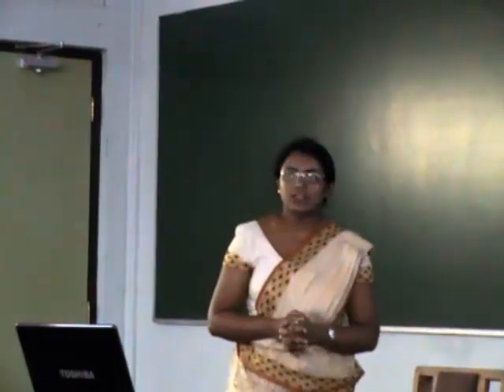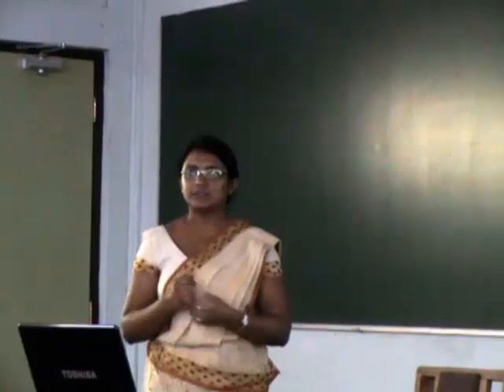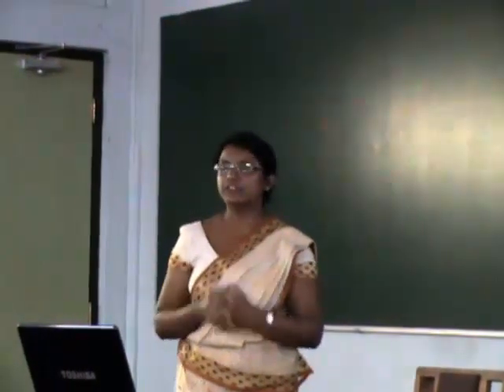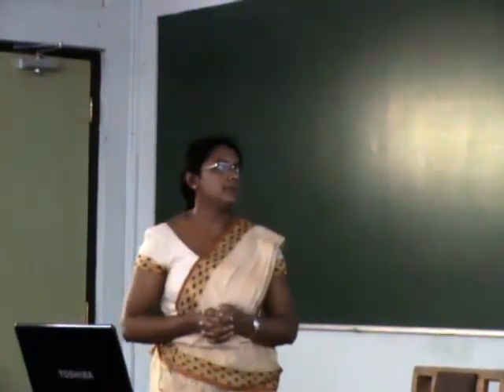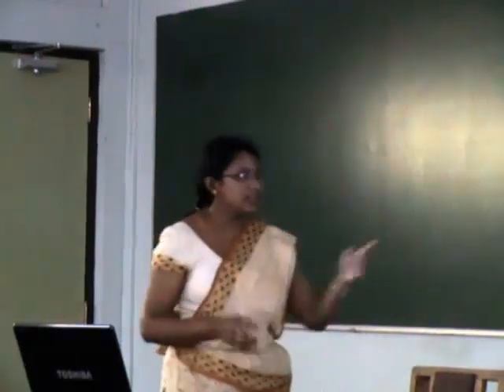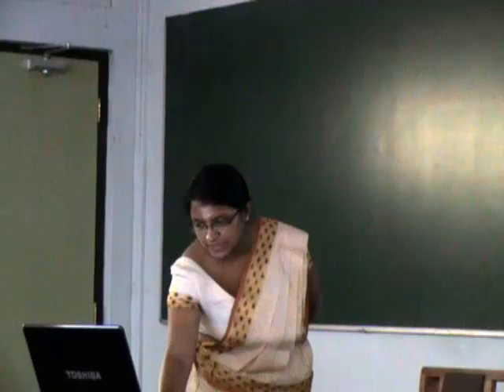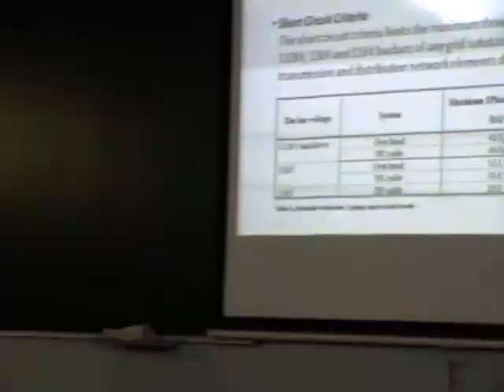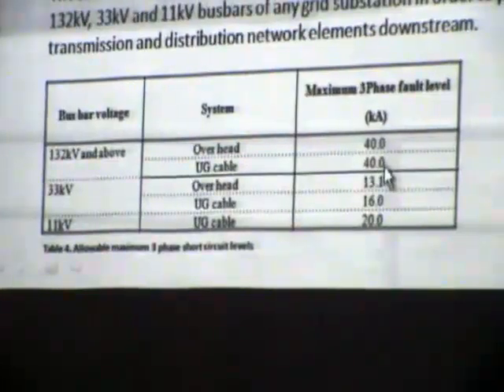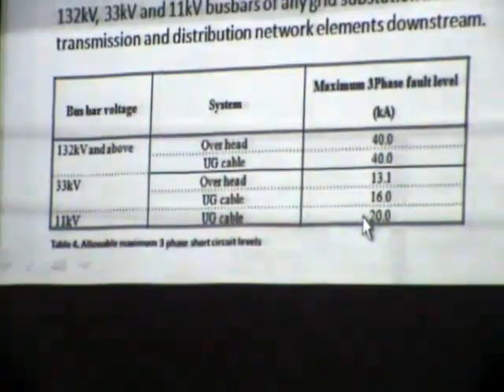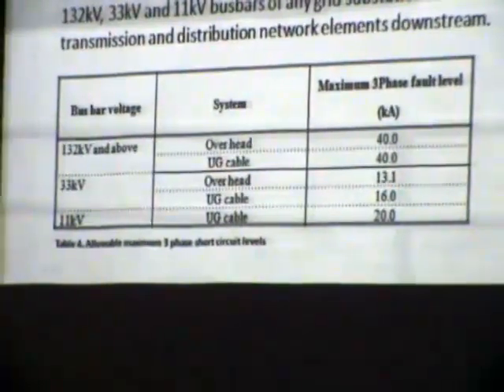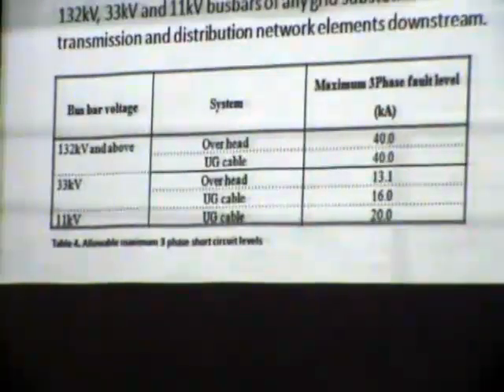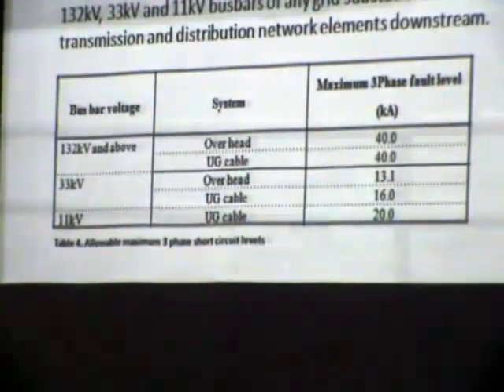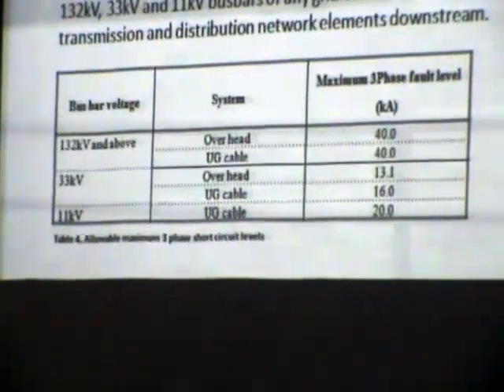Short circuit criteria. If you have visited any grid substation, you may see that every equipment in the grid substation has a maximum short circuit capacity level. So these are the typical short circuit capacity levels in the Sri Lanka system. For 132 and above, if it is an overhead line, that is 40.0 kA. For the 33, 13.1 rated. That means that equipment can handle only up to that maximum short circuit level. So we have to check whether our grid substation is exceeding that maximum level or not.